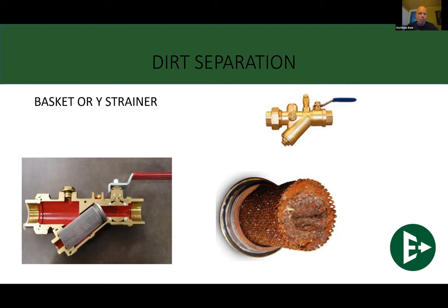Not to mention the fact that the mesh on these Y strainers is quite big actually. It's like a millimeter. So all the particles have to be at least bigger than that to get caught. It doesn't do anything for the small particles of dirt inside of a system that build up and accumulate on hotspots. Second of all, these things are quite difficult to clean. Getting that little cap off of your basket, usually with regards to systems, these things never come apart. They never get cleaned anyway. They don't get cleaned until the whole system fails. And in that case, they don't get cleaned, they usually just get replaced. So like I said, not a fan of them for that reason. They're complicated to clean. They don't catch the small particles. And as soon as they do start to work, it makes the whole system less efficient. I am not a fan, but you do whatever you want.